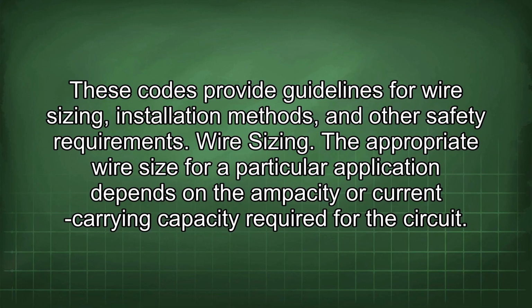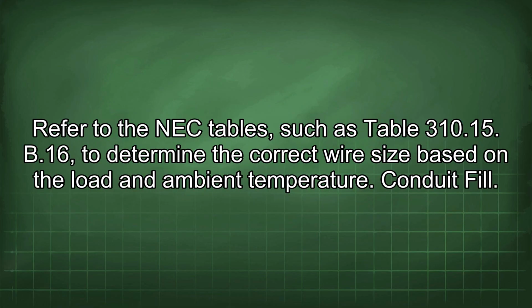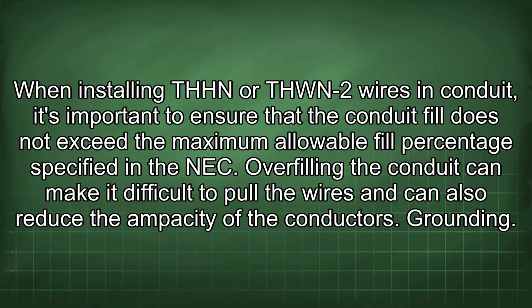Wire sizing. The appropriate wire size for a particular application depends on the ampacity or current carrying capacity required for the circuit. Refer to the NEC tables such as Table 310.15(B)(16) to determine the correct wire size based on the load and ambient temperature. Conduit fill. When installing THHN or THWN-2 wires in conduit, it's important to ensure that the conduit fill does not exceed the maximum allowable fill percentage specified in the NEC. Overfilling the conduit can make it difficult to pull the wires and can also reduce the ampacity of the conductors.